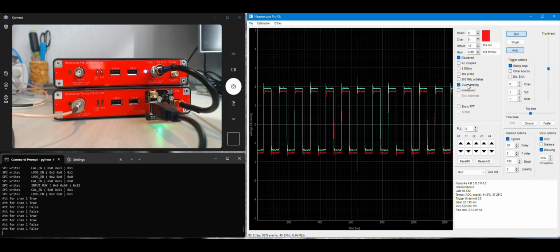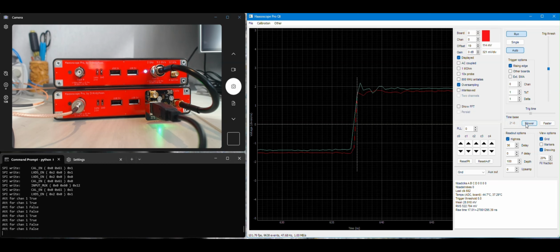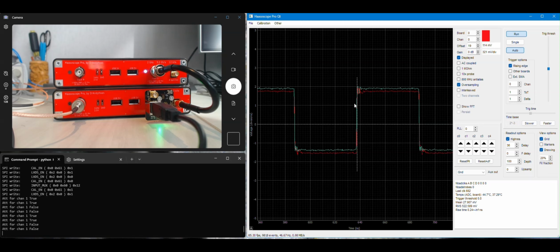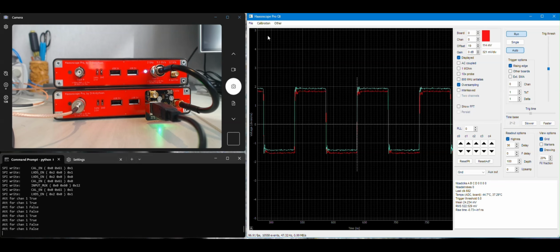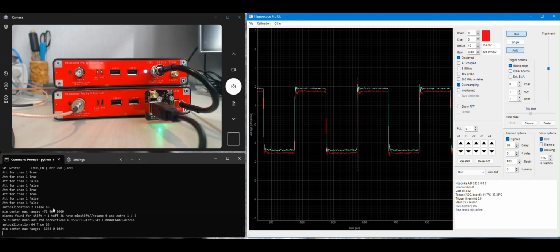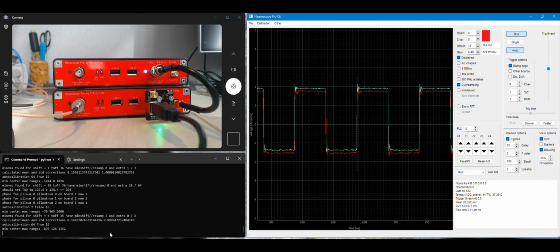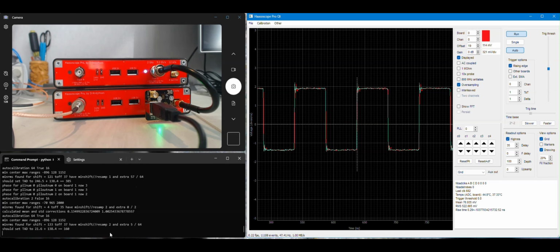Once you're doing that, you can see that you've got the signal duplicated and synced up between the two scopes. Now the signals are still a little bit offset from each other in voltage, and they're not perfectly synced up in time either, although they're pretty close. So to fix that, we have this handy auto calibration feature. So you just get your signal, maybe a few edges is kind of good and helpful, and then you just go up here, calibration, oversampling calibration, and you'll see what it's doing is basically fitting one signal to the other and adjusting the gain ever so slightly and the offset ever so slightly of one signal so that it matches the other one as best as possible.